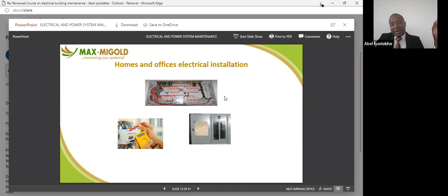We have the ring circuit, a complete ring running from the CCU, that is the consumer control unit, to all the sockets and back to the consumer control unit. That's the ring type of installation. They start looping it, but the disadvantage is that you are overloading the source of that supply.